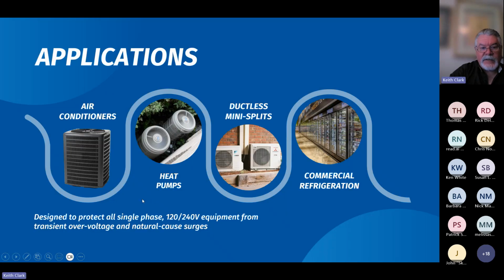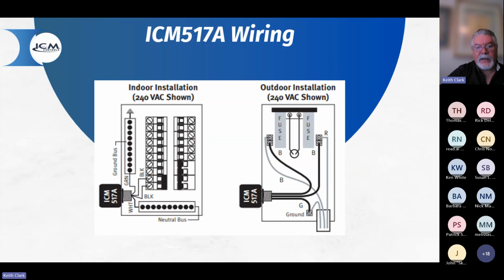Applications far exceed these: air conditioners, heat pumps, ductless, commercial refrigeration, keep naming it, because the way these things wire in, you can put it on the panel, and type 2 will serve as protection for one breaker. So you could put it on your refrigerator, or maybe you have some big TV that you value, or maybe it's a sound system of some type, or any type of device that you want to protect. Refrigerators, those aren't cheap these days. You could put one of these on that breaker and protect your refrigerator. But it's designed for a single device or a single breaker, a type 2. A type 1 surge protection device can be used as whole panel protection.